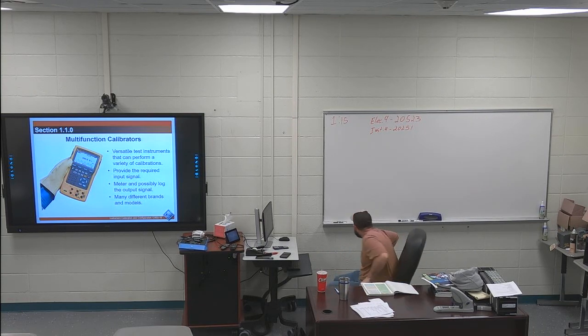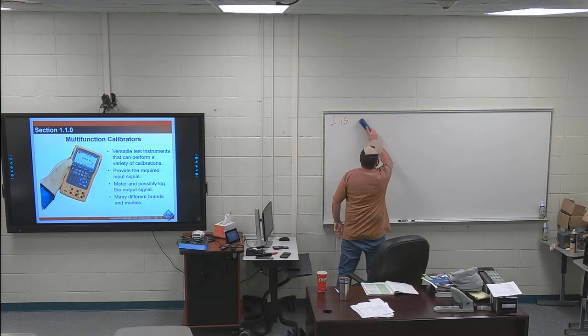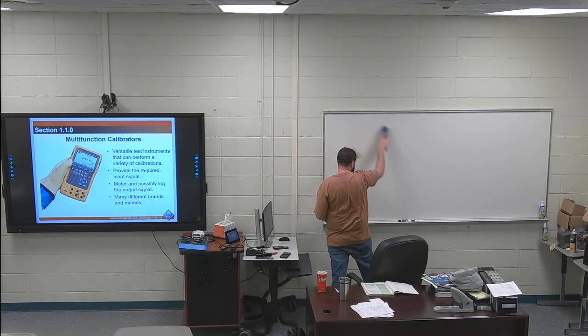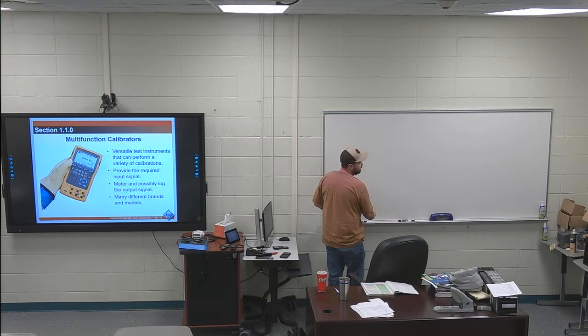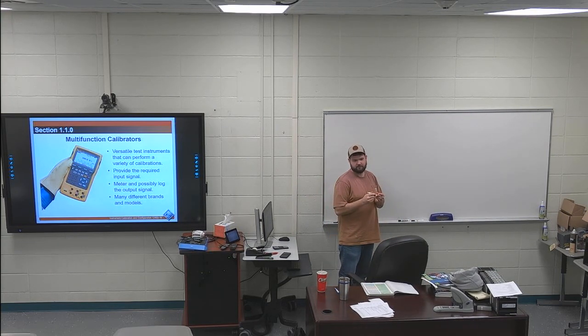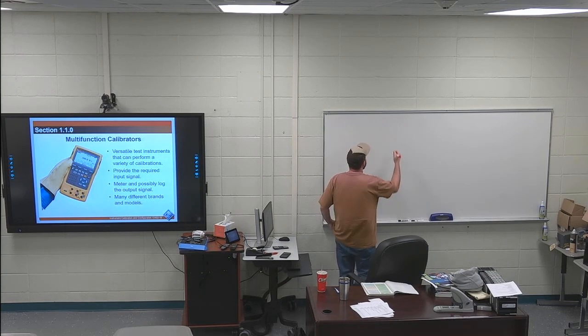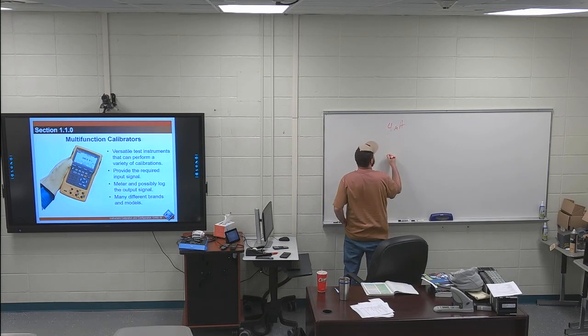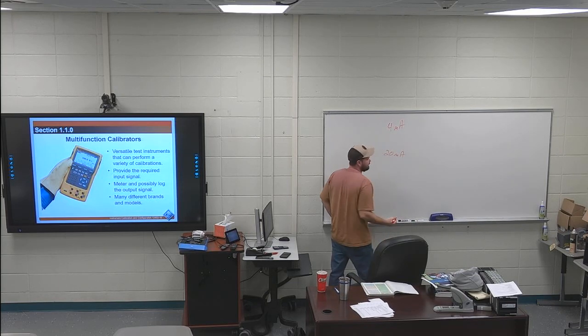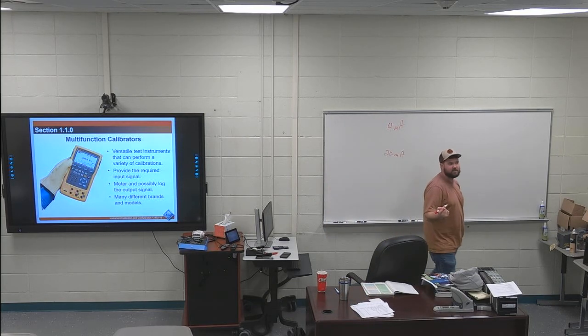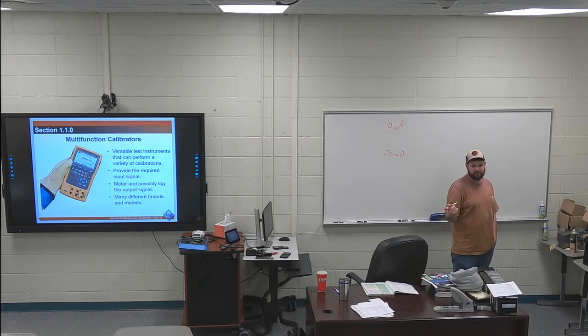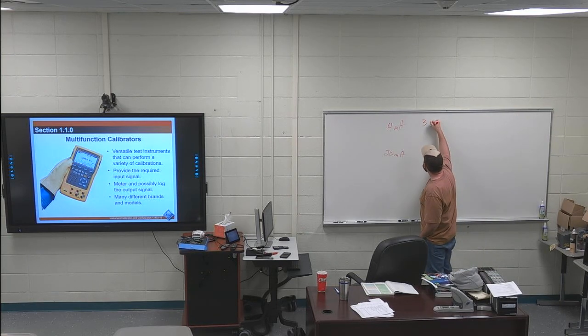5-point calibration, or I guess I can write it like this. So what's our most common instrumentation signal? 4 to 20, right? 4 milliamps to 20 milliamps. You remember what the range was for that control valve, PSI wise? 3 to 15. So 3 PSI to 15 PSI.